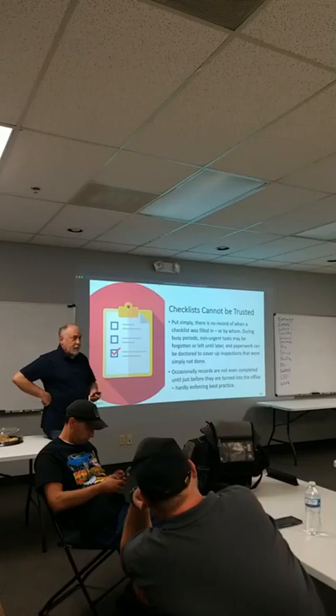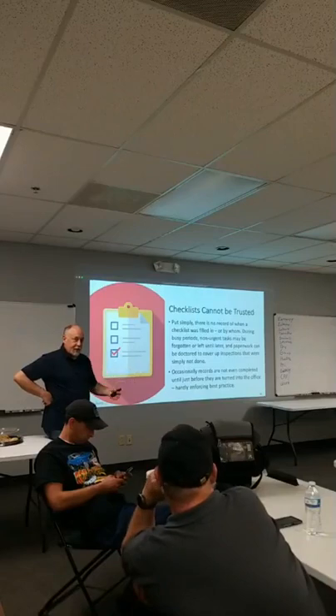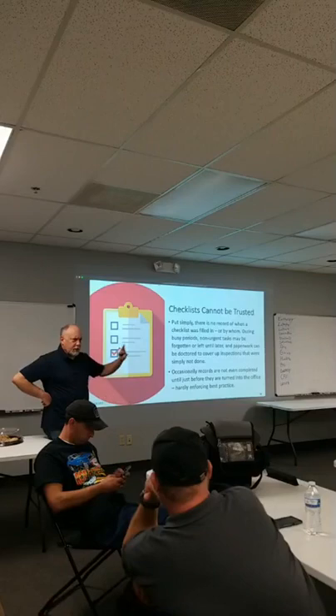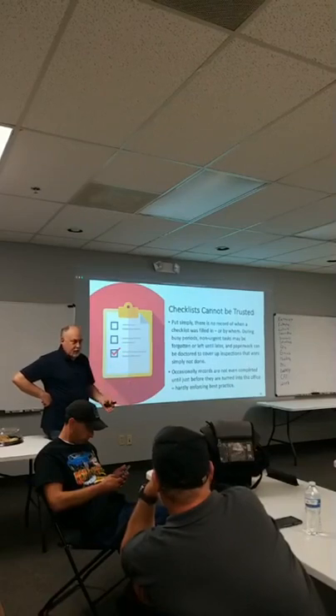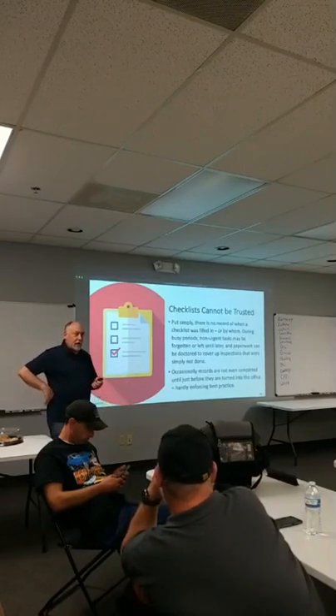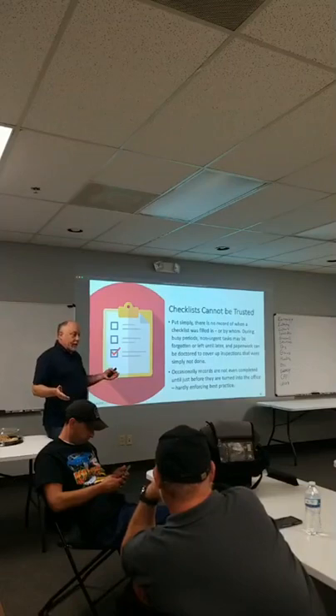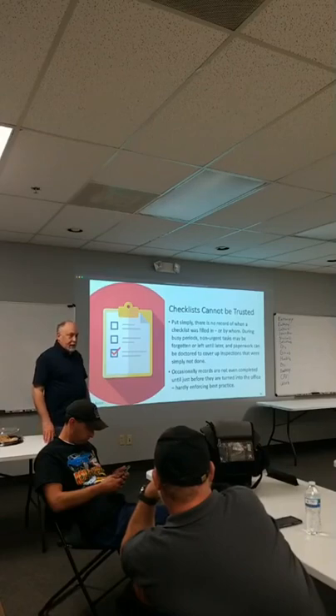And sometimes it was for non-nefarious reasons. Somebody wanted to learn a control system, and they were going out to a job that had the control system, but they were supposed to be out checking 24 rooftop units. And they felt like they were never getting the time on the control system, so they're there quarterly. Somebody else is checking them, and they copy down the check sheets and record them. This kind of stuff happens all the time, right? And we've got to realize that when I got out to the job the first time, I'm finding 29, 30 problems on a job, and I'm thinking, okay, this is happening way more than we think it is.